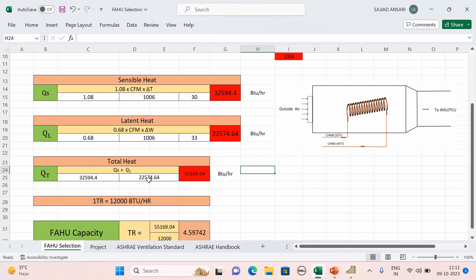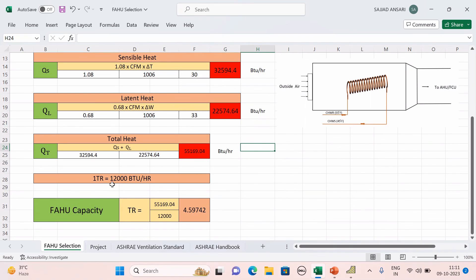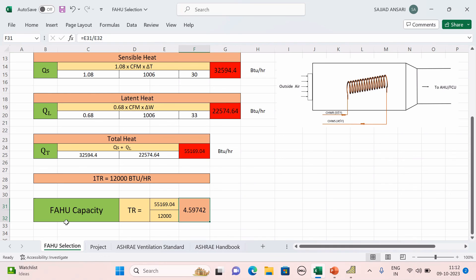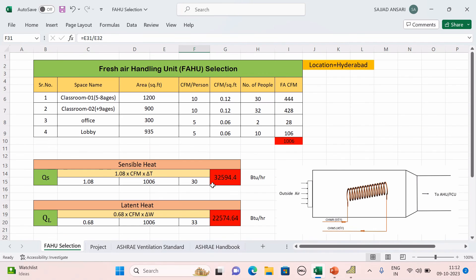Using ΔW = 33, the latent heat is calculated. Adding sensible and latent heat gives total heat = 55,169 BTU/hr. Since 1 TR = 12,000 BTU/hr, dividing: 55,169 ÷ 12,000 = 4.59 TR. So the capacity of this FAHU is approximately 4.6 tons. This is how we do the fresh air handling unit selection. I hope you all enjoyed this session — see you in the next one.